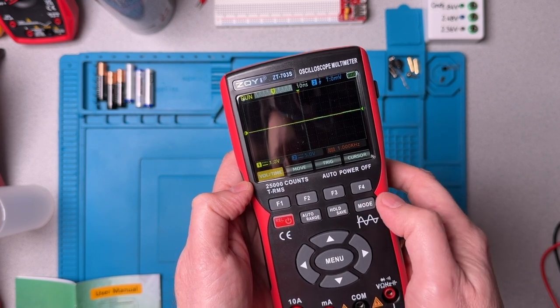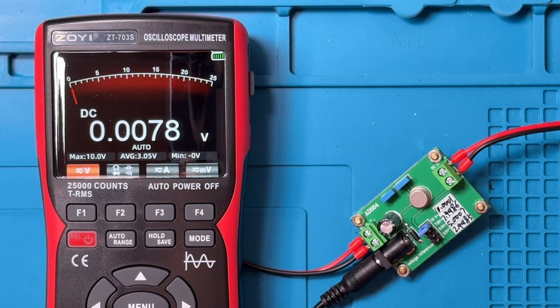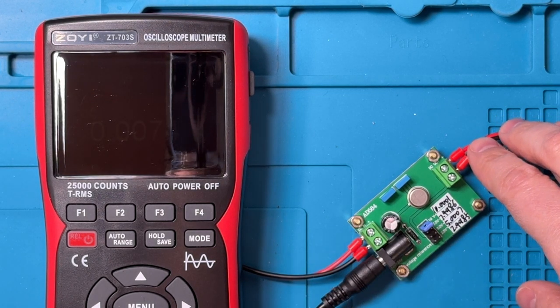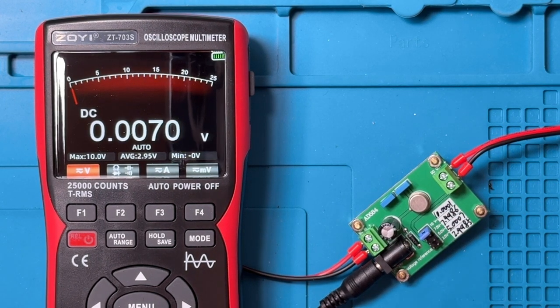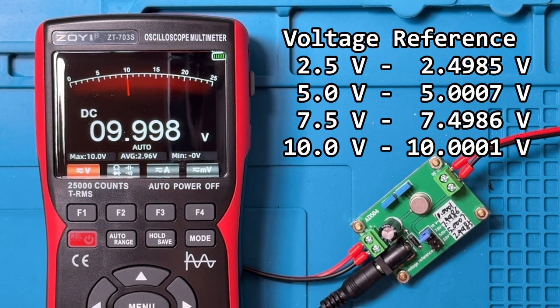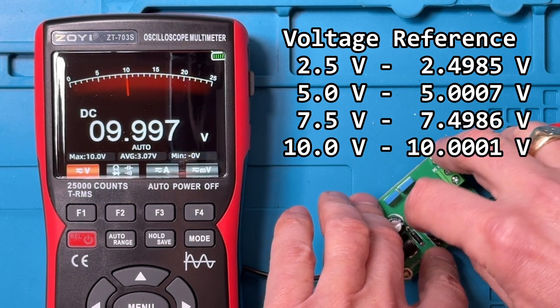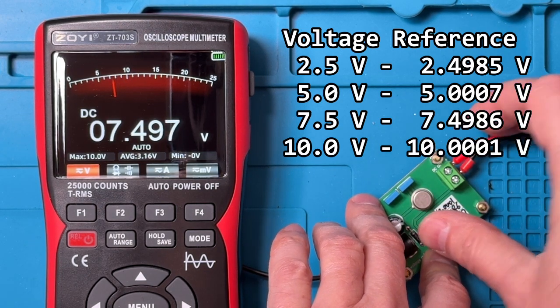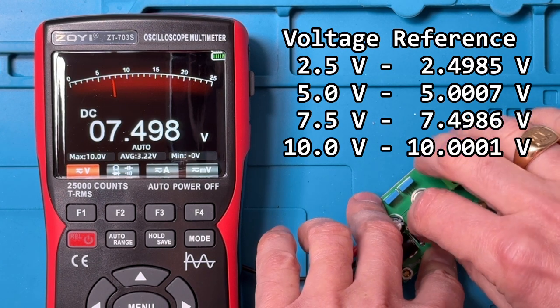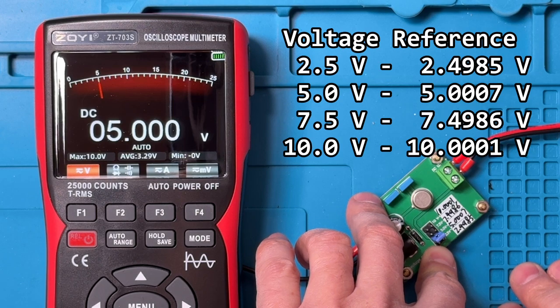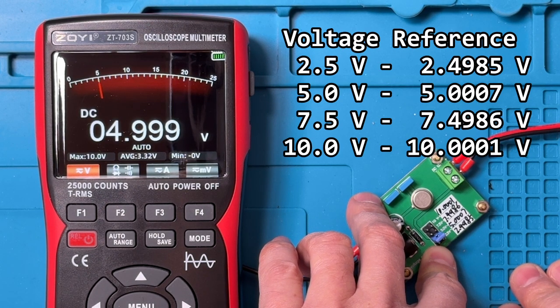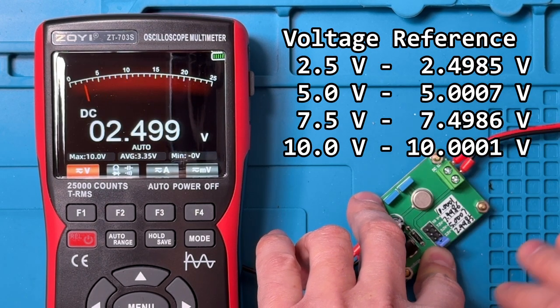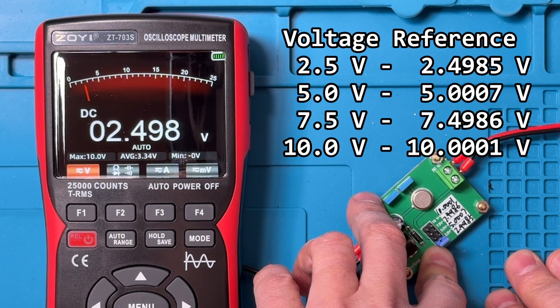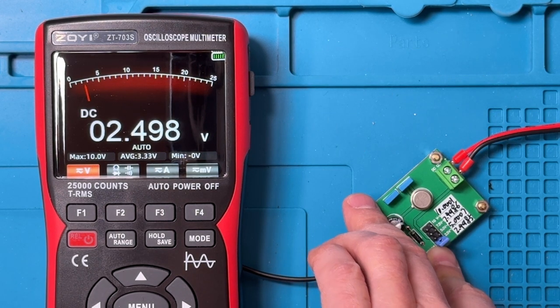Right now we're in oscilloscope mode, but the first set of tests we're going to do are going to be in multimeter mode. So that's here. We'll start with DC volts, and this is a reference source, and it's not on yet. The calibrated values are in the overlay. So this is 10 volts, and that's a little lower than expected. This is 7.5 volts. That's a very good reading for 7.5. This is 5 volts. That's a good reading. And 2.5 volts. Once again, another very good reading. So, very good performance for DC voltage.